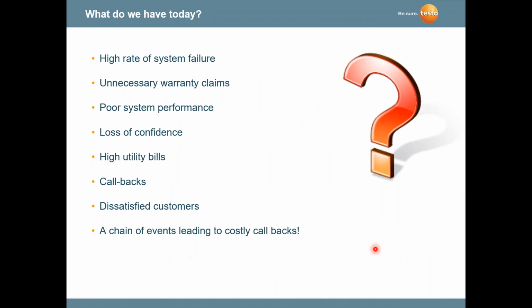And most of you who are using Testo may have noticed that you may have some old probes, and when you turn your instrument on after using it for 2 or 3 or 4 years, in ambient air, the temperature will read almost plus or minus 0.1, a tenth of a degree difference, when the two temperature probes are next to each other in ambient air.